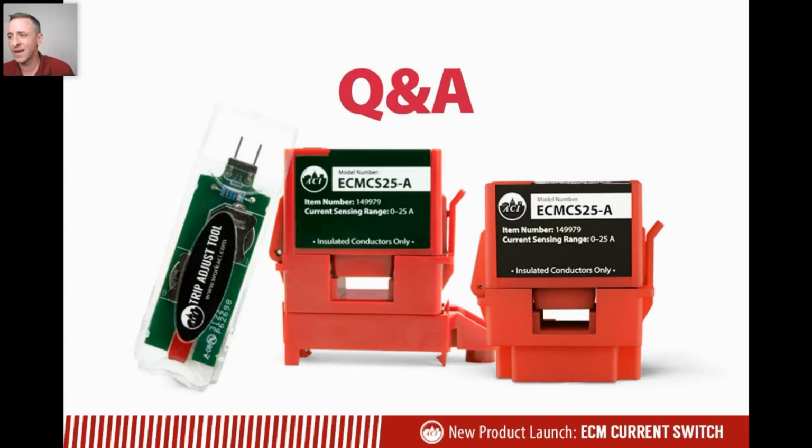Another question is, is 25 amps the max? Yes, for this new ECM current switch, 25 amps is the maximum that this device can handle. And the adjustable trip point is from 0.075 amps up to 0.5 amps. In our experience, and from the research and feedback we've had from customers over the years, we see more and more ECMs at the very low end of current that are drawing very little current, and not so much at those high levels of current. But yes, 25 amps is the max that this can handle.